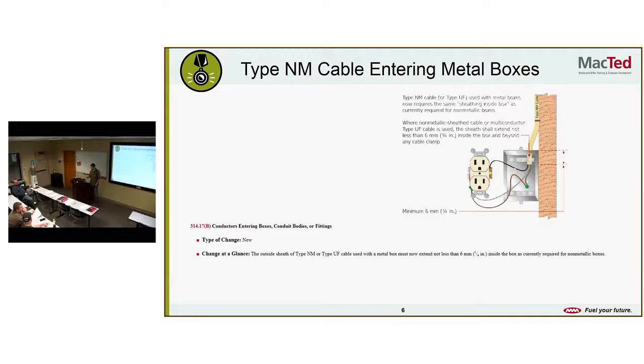All right. Type NM cable entering metal boxes. Everybody know what type NM cable is? Romex. So this is something that pertains to your house, most likely, since Romex is not allowed in buildings, at least to my knowledge. Romex isn't allowed in buildings, is it? It is, three floors or less. Small buildings, okay. Conductors entering boxes: the outside sheath of NM or UF cable used with a metal box must now extend not less than 1/4 of an inch inside the box, as currently required for non-metallic boxes. So if you're going to run Romex into a metal box, you've got to have a little bit of sheathing in there. Can't just drag it in with bare wires into a metal box. Sounds like a smart move.